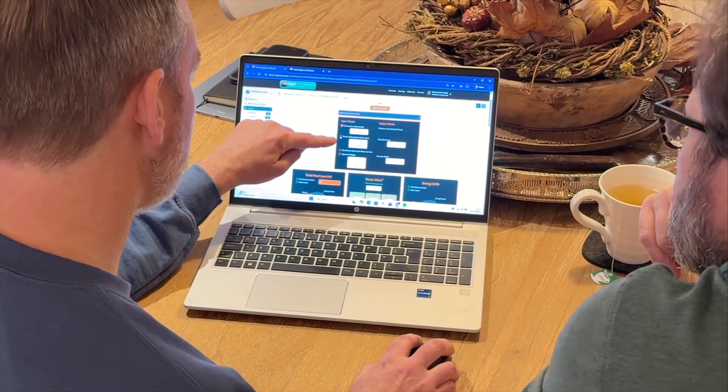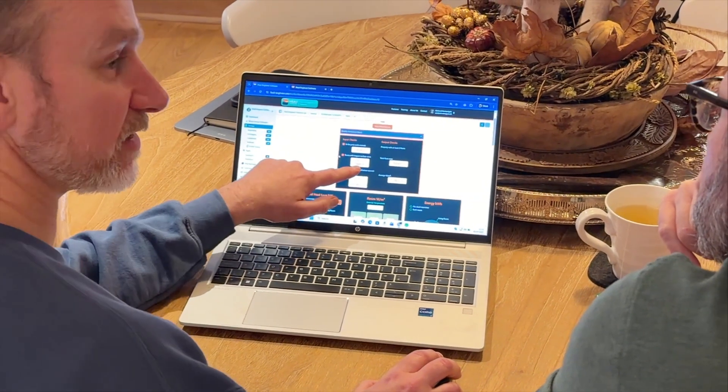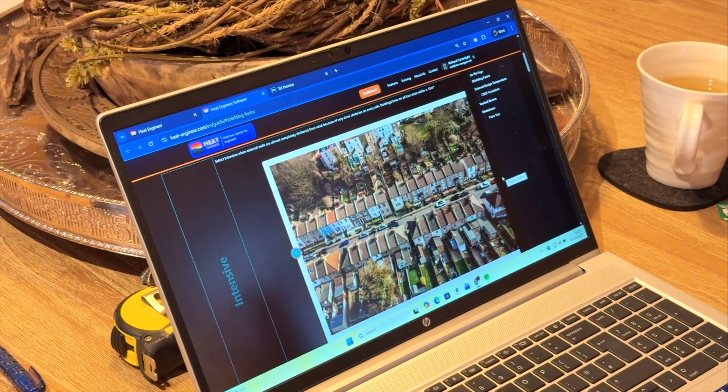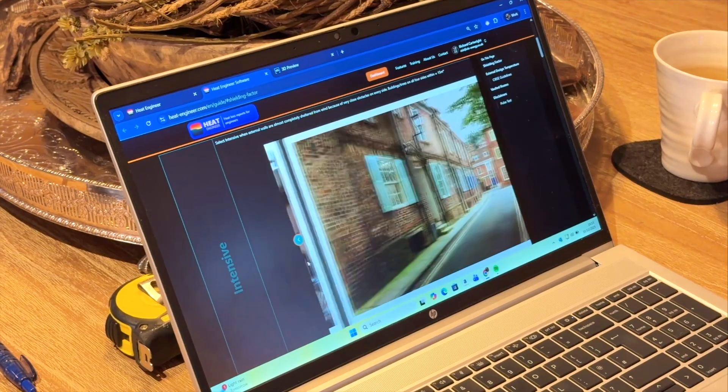What is the benefit of an installer using an Excel spreadsheet versus Heat Engineer software? Reducing human error is a big factor. Heat Engineer has various steps highlighting if someone has entered a maximum or minimum number out of range, or if building materials are missing for a particular element. For example, if someone enters an external length of 5.3 meters in Excel, it won't ask if you're missing a material, whereas our software will flag that you need to state a material because a dimension exists without one. There are also quality assurance checks - like verifying the postcode is correct, since that affects the external design temperature, and flagging the highest U-value used.